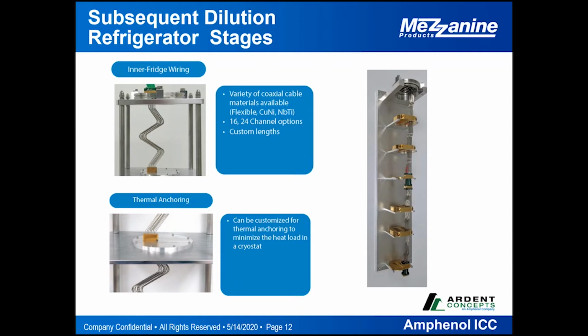From a thermal anchoring standpoint, we can build into our connector sets and into our cable sets options for thermal anchoring to minimize the heat load in the cryostat and to ensure that you have proper thermal anchoring out through the system as you go between stages. In this case, on the right-hand side, you can actually see a full system that was built from the top of the room temp side of the dilution refrigerator all the way down to where the shielding can or the sample exchanger would be loaded in. And through this, we have various stages of thermal anchoring.